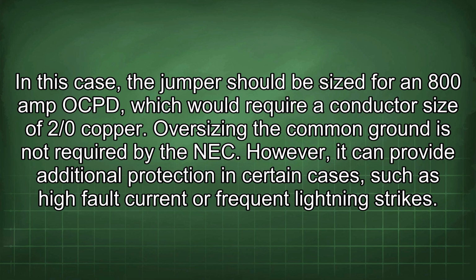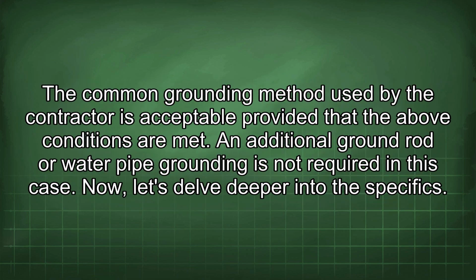However, it can provide additional protection in certain cases, such as high fault current or frequent lightning strikes. The common grounding method used by the contractor is acceptable provided that the above conditions are met. An additional ground rod or water pipe grounding is not required in this case. Now let's delve deeper into the specifics.